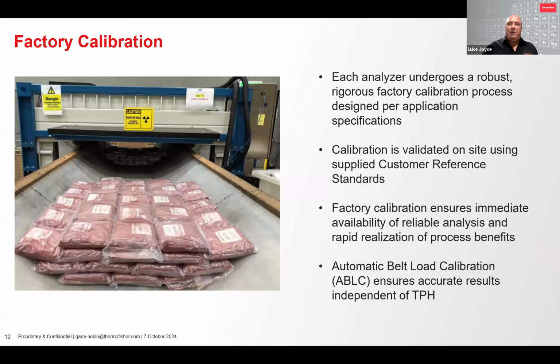So calibration methodology is also critical to ensure accurate online analysis that accounts for the full range of material flow conditions and chemistry and mineralogy variability. You might be familiar with the 5 Ps: proper preparation prevents poor performance. This encapsulates our approach to online PGNAA analysis. The first step is in the preparation and gathering the relevant conveyor and material flow conditions and information on the chemistry variability and mineralogy variability.